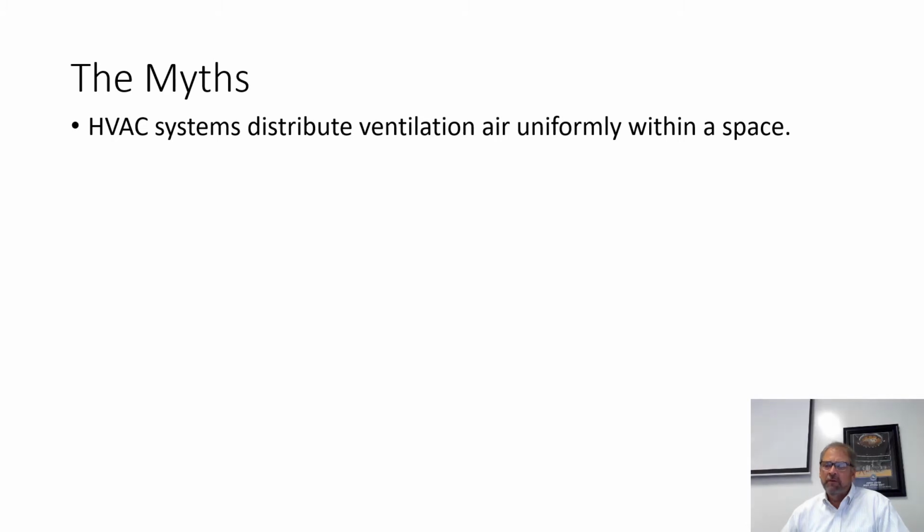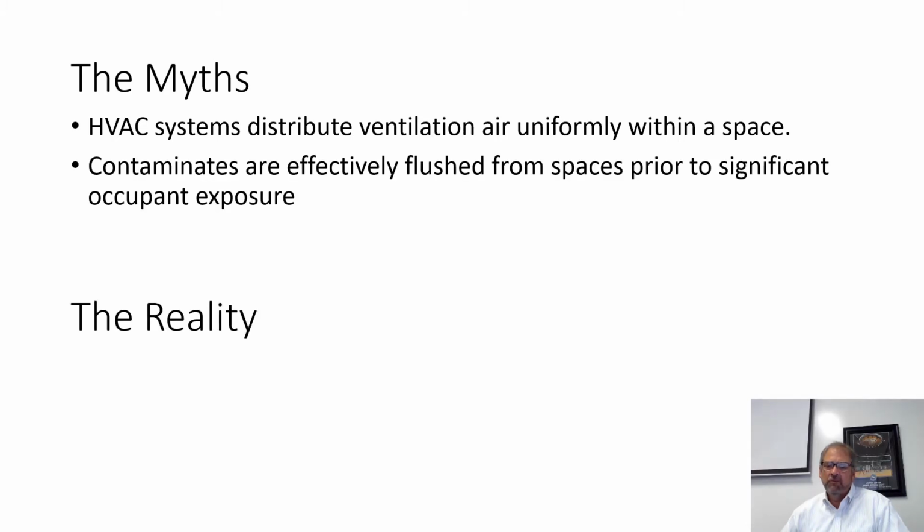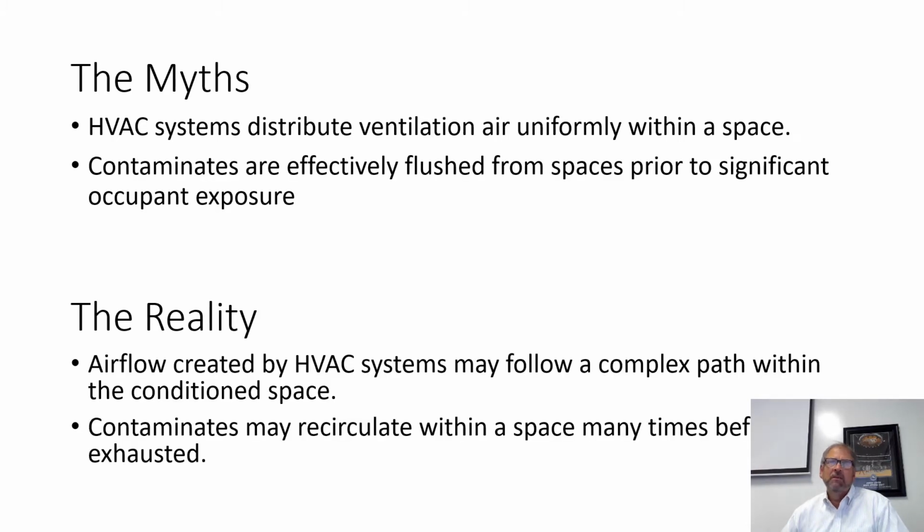So for my 35 years of doing this, I've always thought that if I introduce enough clean air into a space, it will displace the dirty air, which will leave the space, and I can have a clean environment. The reality is, unless I'm very careful about how I introduce that clean air, the dirty air will stay within the space for a very long period of time and just float around for hours, sometimes over 24 hours. Particulates may remain in a space.